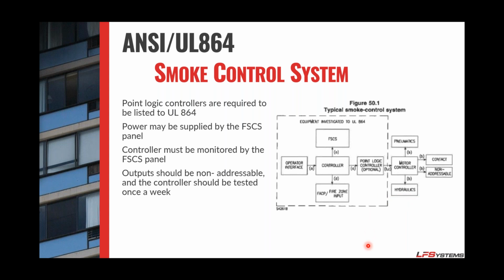Where this becomes an issue, primarily on stairwells, but I can definitely see it on elevators as well, is putting a sensor to a VFD and saying, well, the VFD is just a motor control, it doesn't have to be listed. Factually, that is incorrect, because that VFD is now using the internal PID loop, or point logic control system, internal to the drive. It's making decisions, therefore that has to be listed. And to my knowledge, there is not a UL 864 listed VFD available in the marketplace today. That could change, but as of today, no one is offering an 864 listed VFD.